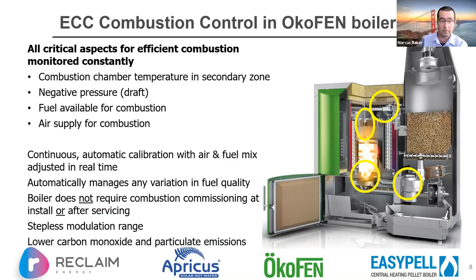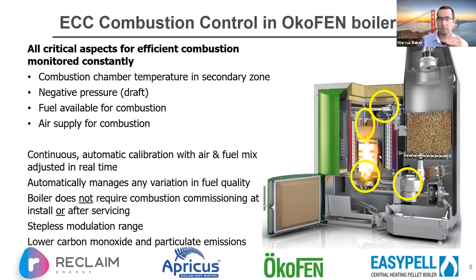It's continuous and automatic calibration of air and fuel. Variation in fuel quality is managed very easily because if you're monitoring temperature and you know how much fuel is going in and how much air, you can determine — for example, if temperature is dropping despite normal fuel input — that you need to introduce more fuel. This is a continuous way for the boiler to monitor and ensure it's hitting optimum conditions.